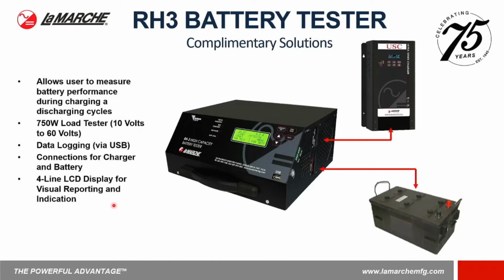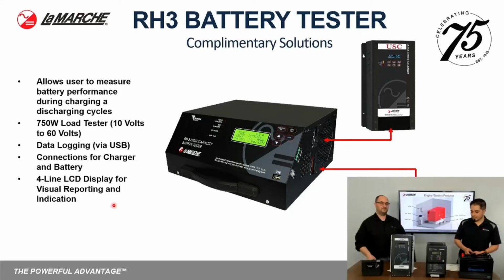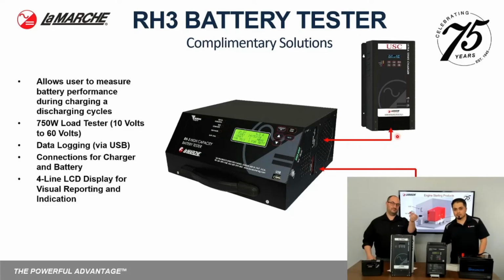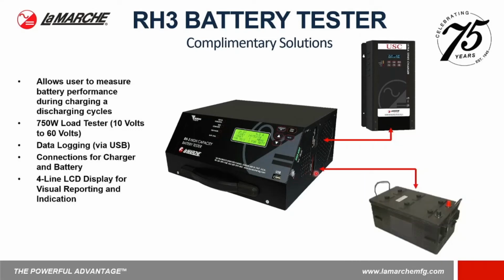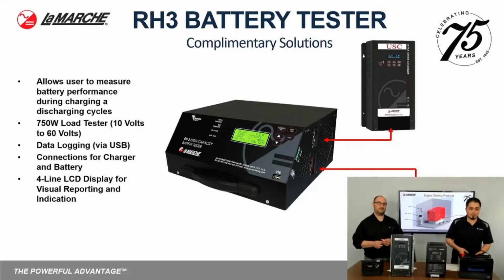A nifty thing about this is that it does have data logging via USB connection, so you can go ahead and obtain that data, pull it out, and look at it on your laptop or through an Excel file. As you can see on the image here, you have your connections via connector from your charger to your battery tester in line, and then also your battery connection directly out as well. So it is something that you can permanently install. Obviously, it'd be better to check it as a trend to make sure your batteries are going in the correct direction, or if they're trending down, you know that it's time for a replacement of your batteries, or maybe something has to be changed with your setup.